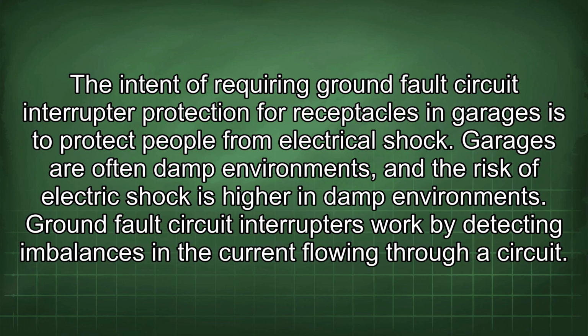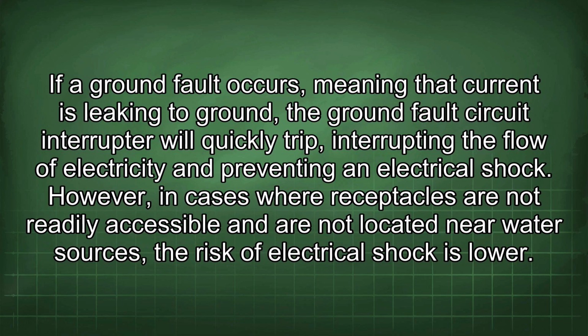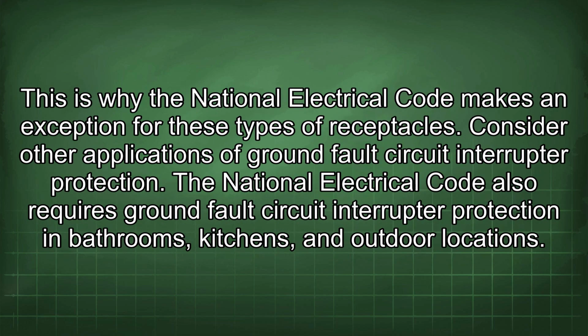The intent of requiring ground fault circuit interrupter protection for receptacles in garages is to protect people from electrical shock. Garages are often damp environments, and the risk of electric shock is higher in damp environments. Ground fault circuit interrupters work by detecting imbalances in the current flowing through a circuit. If a ground fault occurs, meaning that current is leaking to ground, the ground fault circuit interrupter will quickly trip, interrupting the flow of electricity and preventing an electrical shock. However, in cases where receptacles are not readily accessible and are not located near water sources, the risk of electrical shock is lower. This is why the National Electrical Code makes an exception for these types of receptacles.